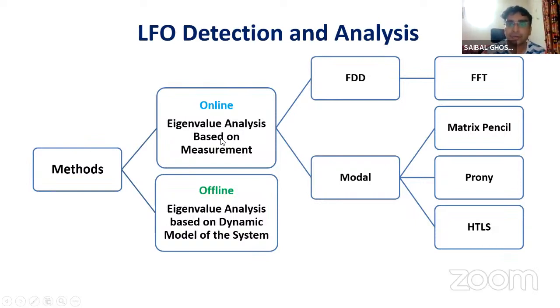And in real time, using measurements from PMUs, because these oscillations are generally very fast compared to the sampling rate of a SCADA system, which updates every 10 seconds. So oscillations of 1 or 2 hertz, meaning a time period of about 1 second, cannot be captured with a 10 second SCADA sampling rate. But using PMU, you will be able to see these oscillations.